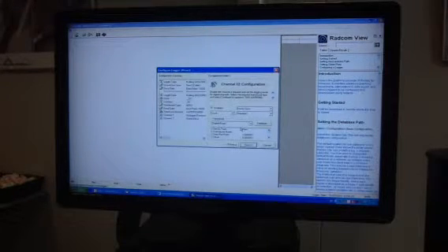Then we go on to channel 2, which is your flow channel, which you can see has digital flow in there. Now we can either have count or event mode. Count mode counts the pulses, and event mode is the time between each pulse. Power save: certain sensors need power supplied to them, which you can have continuous, but it's always defaulted to power save.